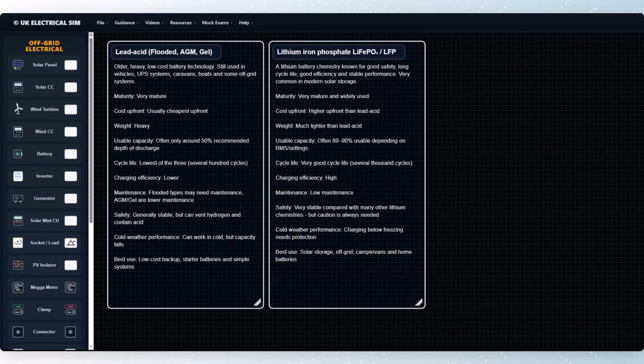Whereas lithium iron phosphate, also known as LiFePO4 or LFP batteries, is now very common in solar and off-grid battery systems. Compared with lead-acid, LFP batteries are lighter, more efficient, have a much longer cycle life, and can usually be discharged much deeper without the same level of damage. They also hold their voltage more steadily during discharge. A major advantage is that LFP is one of the safer lithium battery chemistries. It is more thermally stable than many other lithium-ion types and is widely used for home storage, off-grid systems, portable power stations, and electric vehicles.